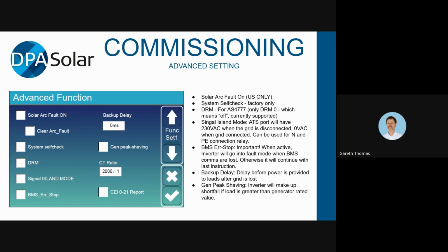Signal island mode. So there's a port on it called the ATS port. And so if you have signal island mode switched on, then when the inverter is not connected to the grid, there will be 230 on the ATS port, which is one of those small connectors like where the CTs are going into. And when the grid is connected, there'll be 0 volts on that. So you could use that if you wanted to have a dynamic neutral and earth link. Do you mean when the grid is available? So if the grid's there, yeah, compared to when the grid is unavailable, the grid goes out. When I've tested it, it seems to be when it's synced to it. So it's not just going to do it when it notices there's voltage there. When it synchronizes with the grid, it will then engage that.